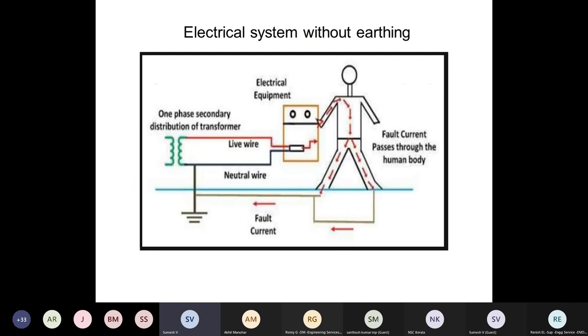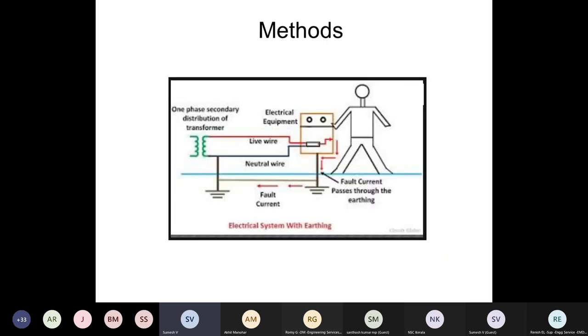Here the equipment is not earthed. That means if any leakage comes to that body, and a person comes in contact with that equipment, they will get shocked. But if it is earthed, whenever that leakage occurs, the fault current flows to the earthing system, makes the protective device operate, making the system safe.